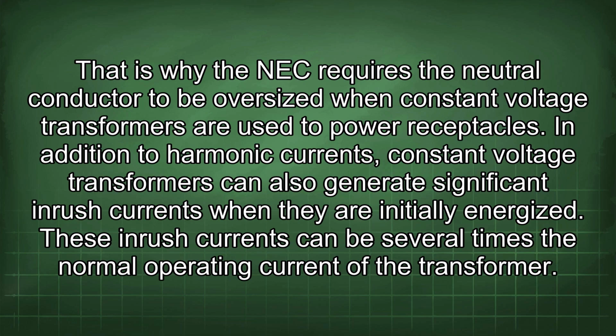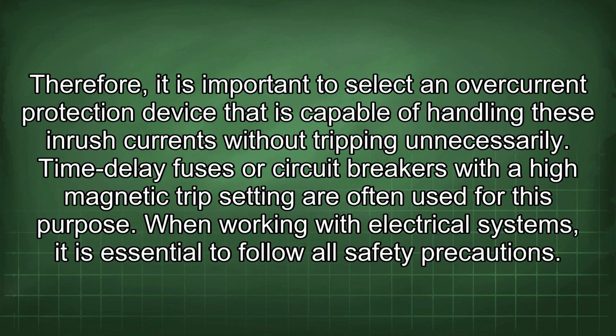In addition to harmonic currents, constant voltage transformers can also generate significant inrush currents when they are initially energized. These inrush currents can be several times the normal operating current of the transformer. Therefore, it is important to select an overcurrent protection device that is capable of handling these inrush currents without tripping unnecessarily. Time delay fuses or circuit breakers with a high magnetic trip setting are often used for this purpose.